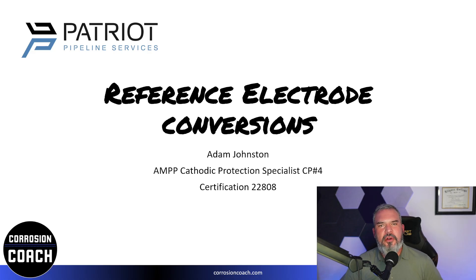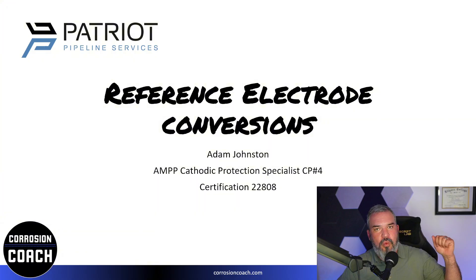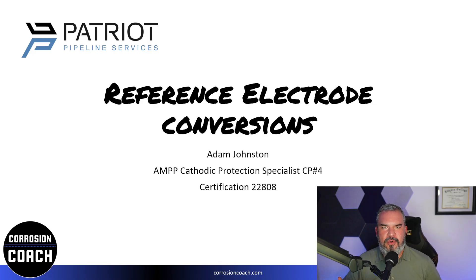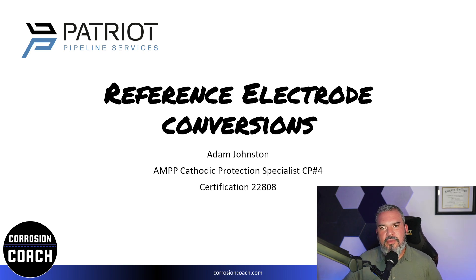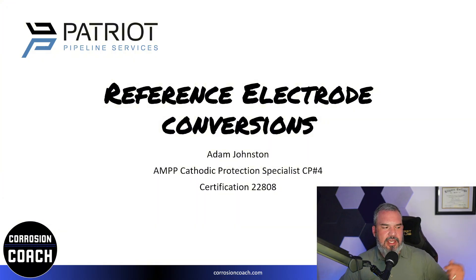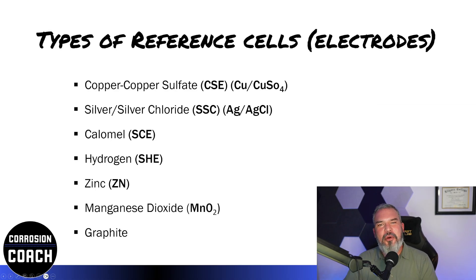Welcome back to Corrosion Coach. We're going to talk about reference electrodes today. When we take pipe-to-soil potentials — which is the way we prove whether we're achieving cathodic protection or not — we must have some type of reference. On the soil side, we have a reference cell or reference electrode on the black, common, or negative side of that meter. We're always taking a pipe-to-soil with a reference electrode on the other side. There are actually multiple reference electrodes.